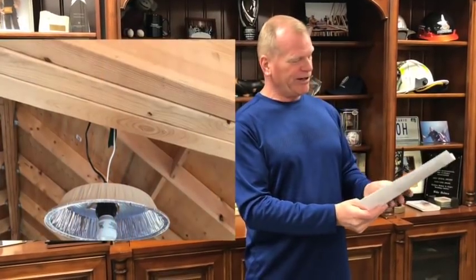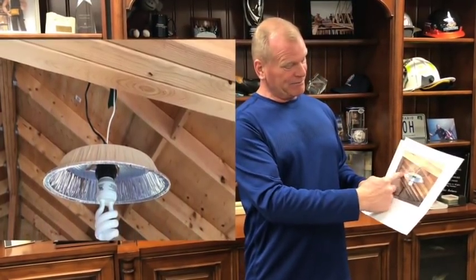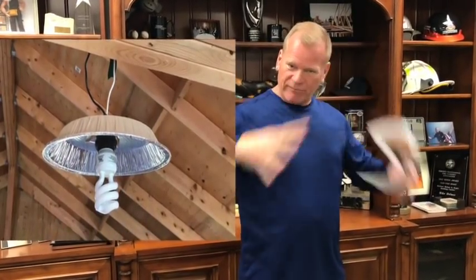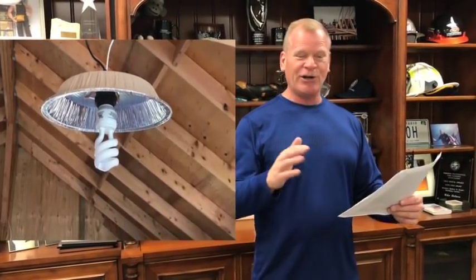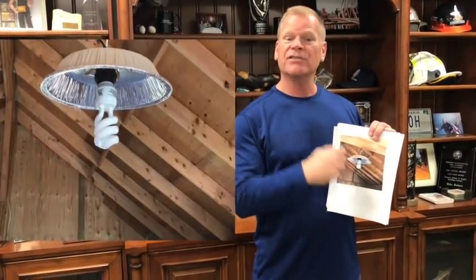Now this one is kind of cute. There's nothing in code that says you can't do it — it's actually kind of smart. They're taking a light and putting it in a tin pie pan, which reflects the light down. Is it smart? No. Does it work? Yes. Is it installed with a proper octagon box? No. Bring in a licensed electrician. Keep sending in your questions and your photos because I'm liking this stuff.